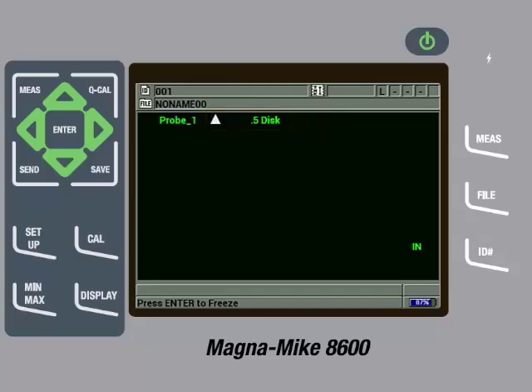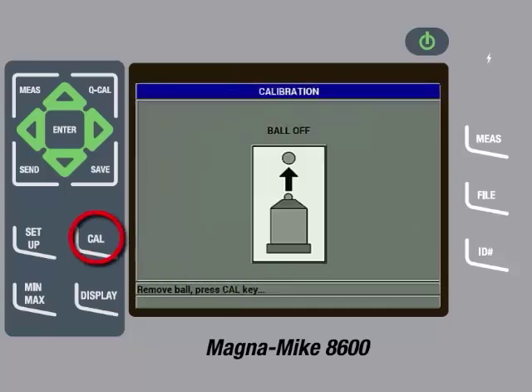Before beginning to calibrate, it is good practice to make sure the wear cap on the probe is screwed on securely and the instrument is in an environment with ambient temperature that is free of magnetic interference. The instrument should be in a location that it will be used in on a regular basis. We can now calibrate. To initiate the calibration process, press the Cal key. The first step of calibration is to perform a ball off. To do this, make sure the disc is removed from the probe tip, then press the Cal key. Once the instrument is done processing, the next step is to perform a ball on.